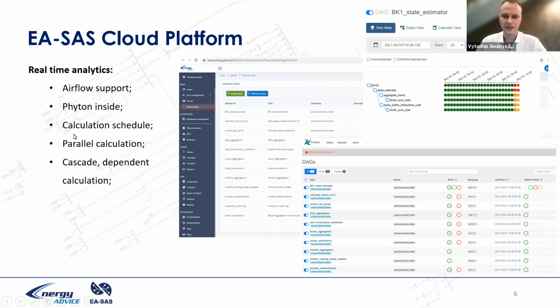If a very complicated calculation exists and you are required to do a lot of calculation, it could be parallelized, with cascade-dependent calculations. In the next slides I will show you projects where we optimized the performance of equipment: district heating, biomass boiler, CHP, cooling machine, glass melting process, and so on. And we provide optimum set points. These set points, in fact, create value. The value is the optimized process where effectiveness is increased and energy consumption is reduced. This is real value, where we can save money. Otherwise, data collection and putting all data in the cloud is just an expense.